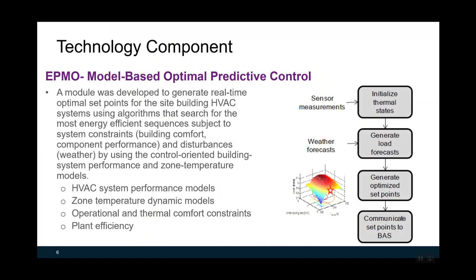The second component is model-based optimal predictive control. An MPC module was developed to generate real-time optimal set points for the building HVAC system, using algorithms that search for the most energy-efficient sequence, subject to system constraints such as building comfort, component performance, and disturbance from weather. This uses the control-oriented building system performance and zone temperature models. The constraints come from operational and thermal comfort constraints, as well as plant efficiency constraints.